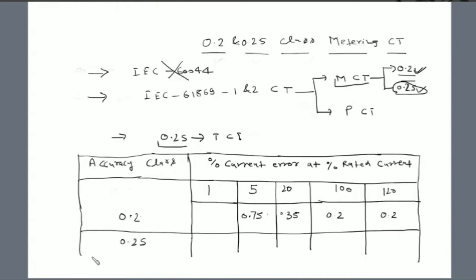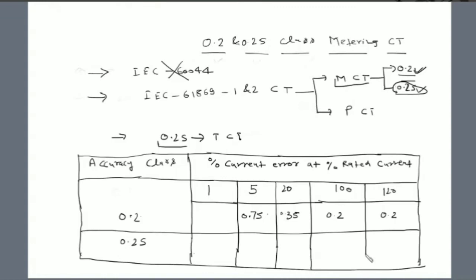For the 0.2S special class CT: this CT can also sense 1% of the rated current, but the error will be higher — at 1% the error is 0.75%. At 5% of rated current, it will produce 0.35% current error. At 20% of the rated current it gives 0.2%, at 100% it gives 0.2%, and at 120% it also gives 0.2%.